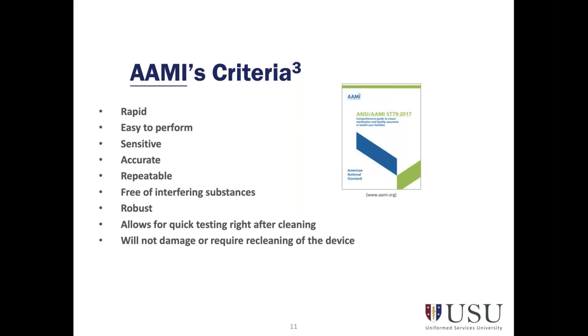It should be robust, meaning the system does not require exacting conditions or time constraints that cannot be achieved in routine reprocessing areas. Also, a cleaning verification system should allow for quick testing right after cleaning and in a way that it will not damage or require re-cleaning of the device. Lastly, and although not officially part of the AAMI criteria, the tool should be objective and affordable.